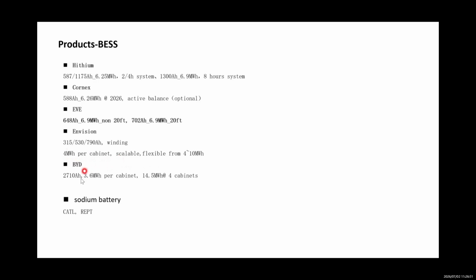For BYD, it's the same concept, but the capacity is 3.6 megawatt hour per cabinet, using 2710 ampere hour battery cells. I think this is the biggest battery cell capacity in the world, the biggest I have ever seen. So the total unit capacity is 14.5 megawatt hour with 4 cabinets.